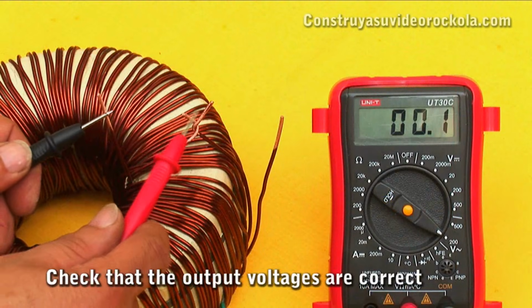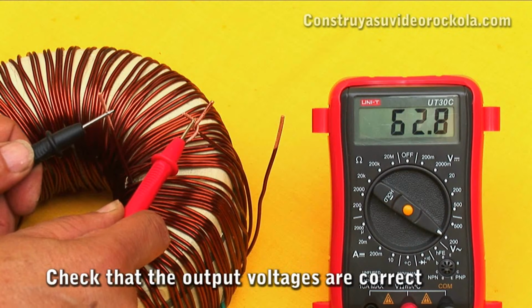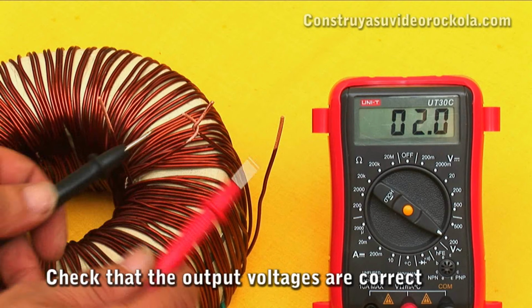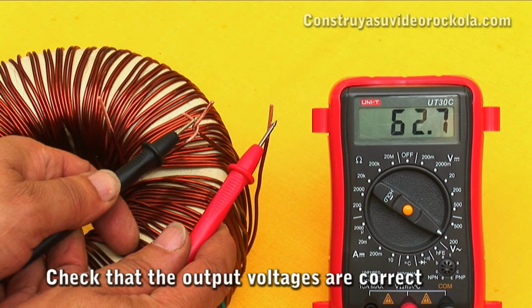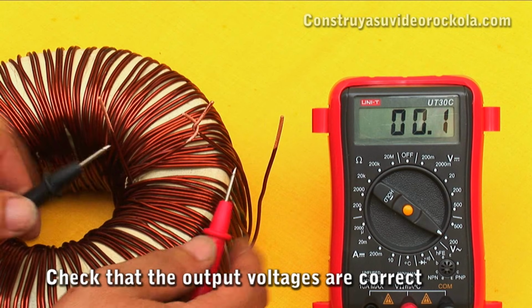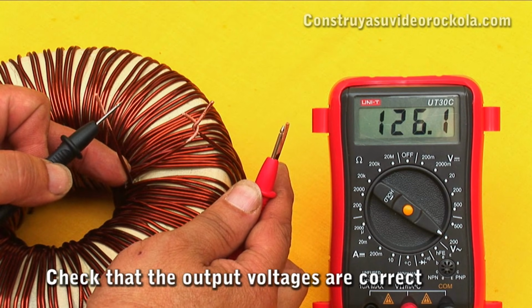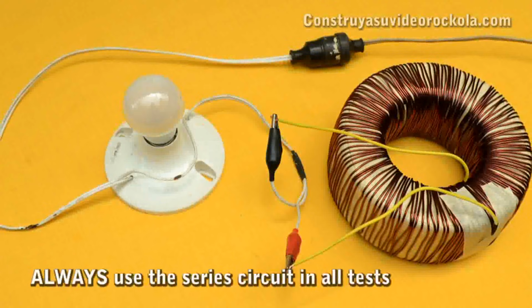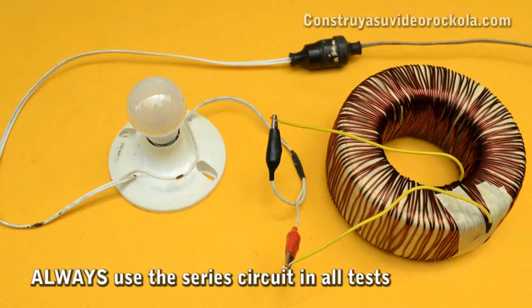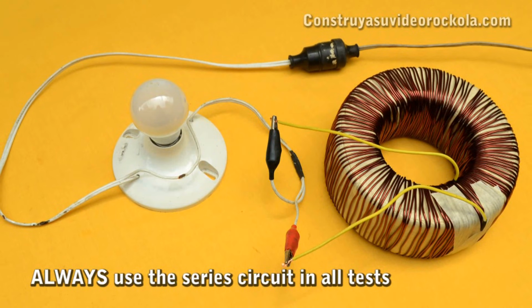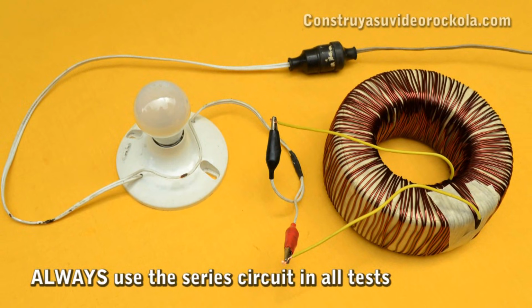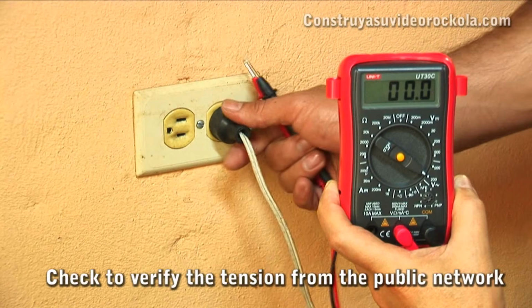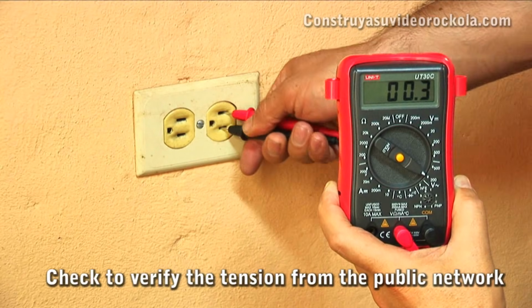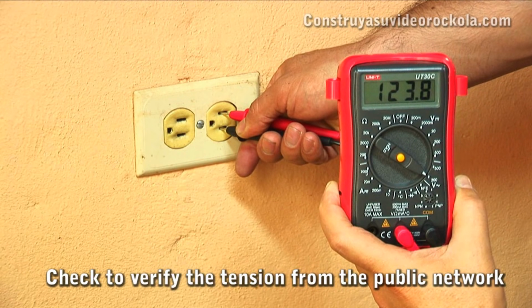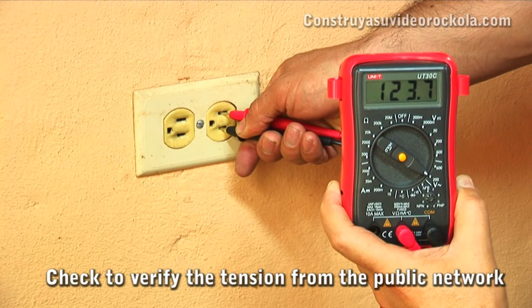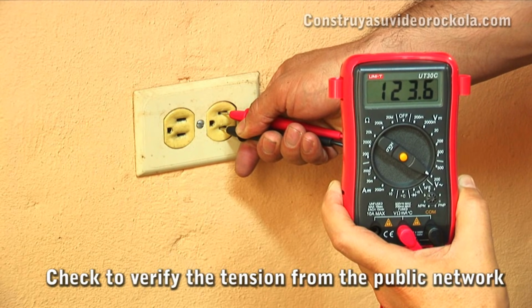The next test is made with a multimeter at AC voltage scale. By measuring between the tap and each of the ends of the wire, the voltage should be fully symmetric. Then measure between the two ends and it should measure twice the voltage. It is imperative to check the central tap connection, always using the series circuit. This is also done for your personal safety. We can see that the voltage gave us 62 volts and we had calculated for 60 volts. We measured the public network voltage and found that the cause is that the voltage of the public network is a little higher.